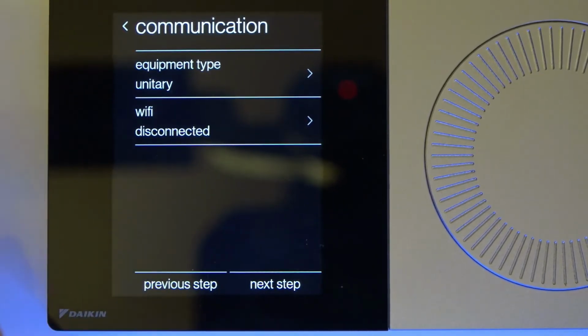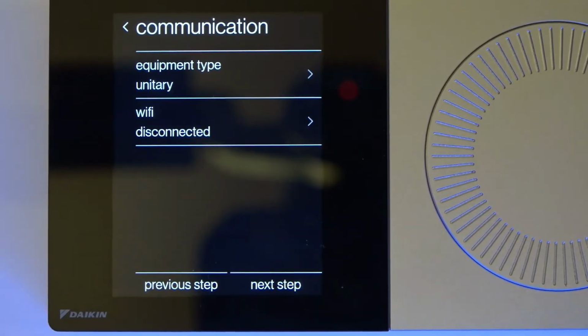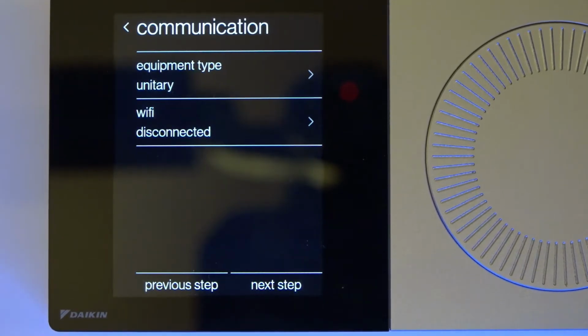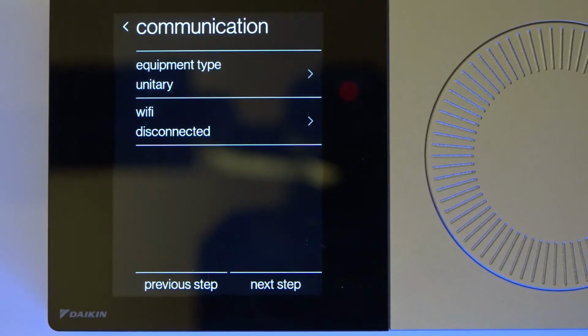Now it says Wi-Fi disconnected. And now I need to do at least one update with this thermostat. If I choose not to leave it connected to a Wi-Fi network, that's fine, but I do need to do at least one update. If you leave it connected to the Wi-Fi network, every so often Daikin will send out an update. It updates the thermostat overnight. Thermostat reboots, and then it goes right back into normal operation.